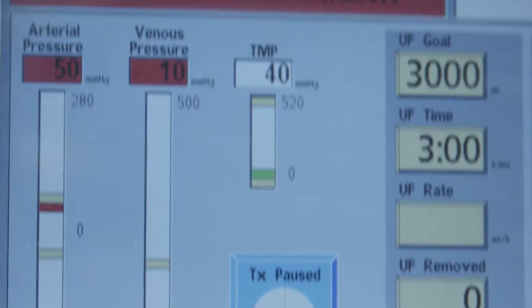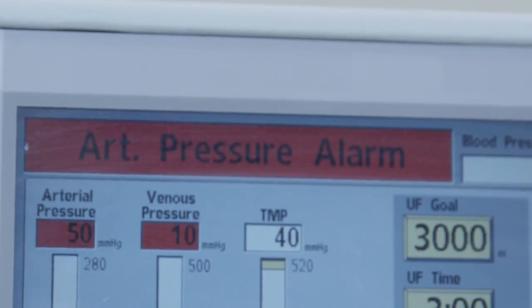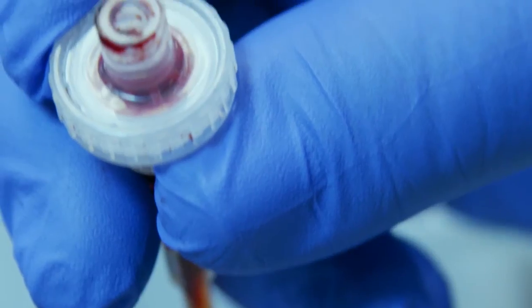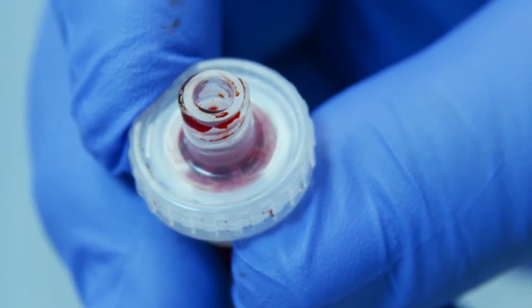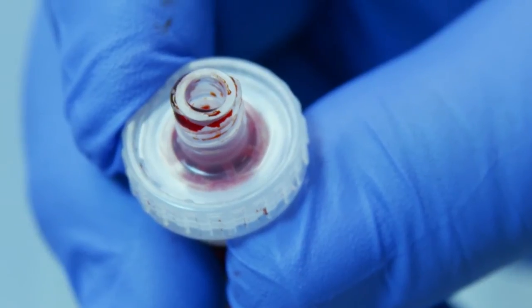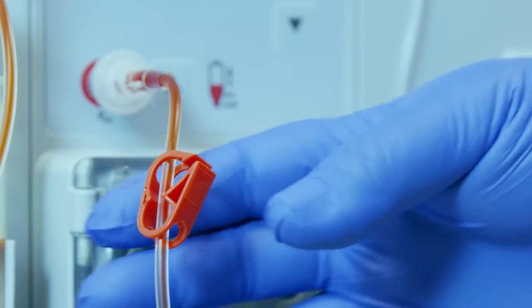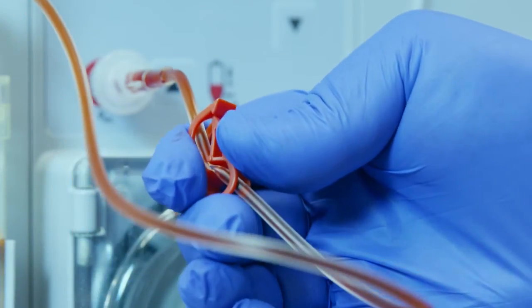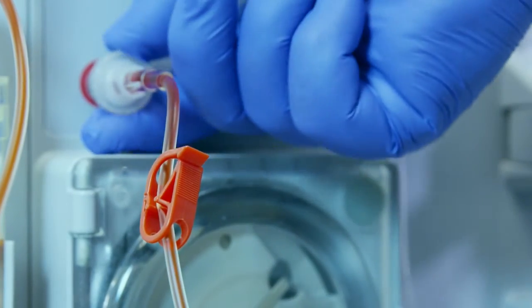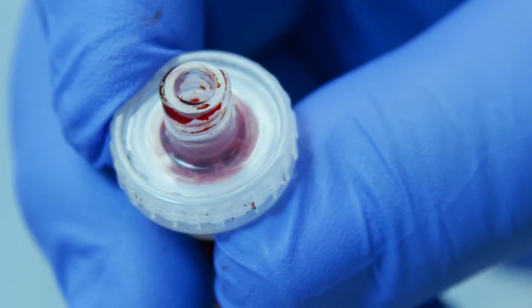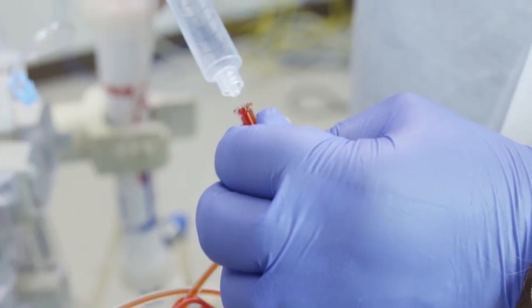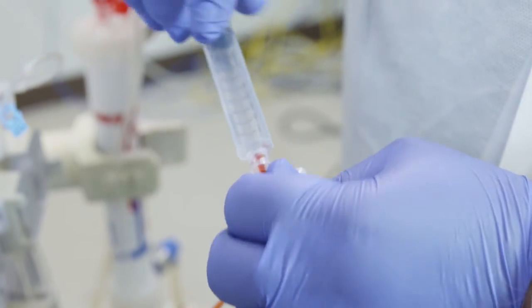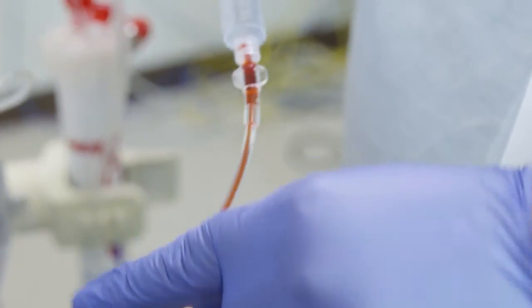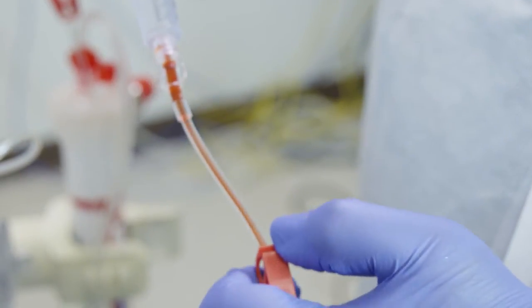If the pressure transducer protector becomes contaminated, it must be changed immediately. Follow your facility's policy and procedures for changing contaminated transducer protectors. Nipro recommends the following steps. Carefully clamp the pressure monitoring line and remove the wetted transducer protector from the machine and monitoring line. Attach a syringe to the monitor line to adjust the level in the drip chamber. Reset the blood level in the drip chamber to 3/4 full.